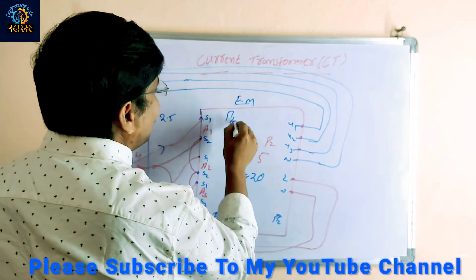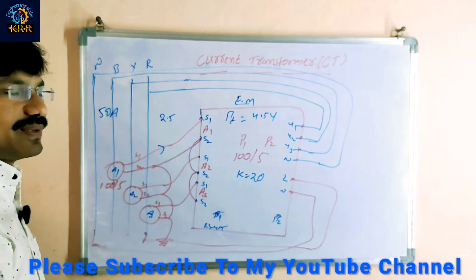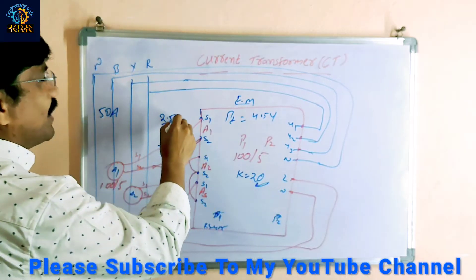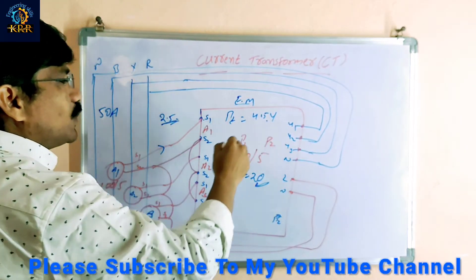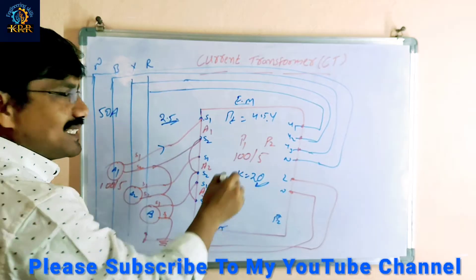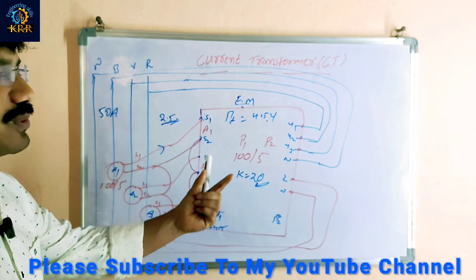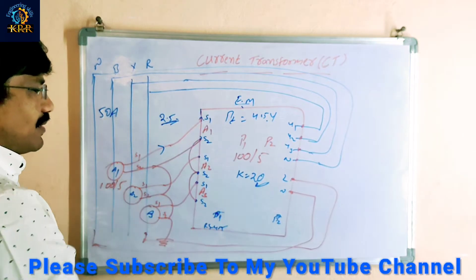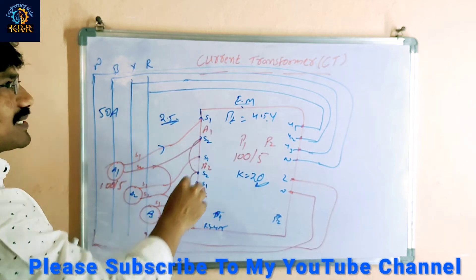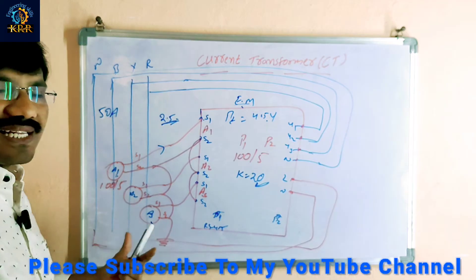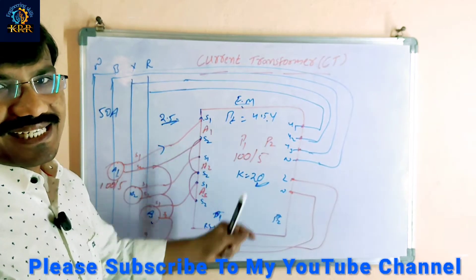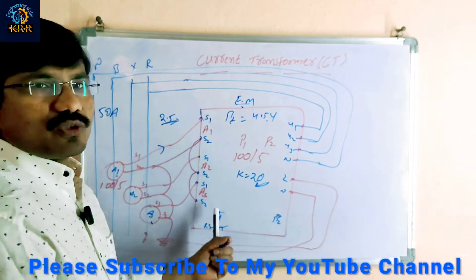PT value — by default 415 volts is entered in this energy meter. We are giving the amps transformation ratio as well. With the multiplication factor and voltage available, the energy meter calculates the power and as well as the energy. It records and displays the energy. Mainly CTs in energy meter areas — measuring areas — are used with CTs sensing the current, passing it through the energy meter, which calculates power and energy and displays it.